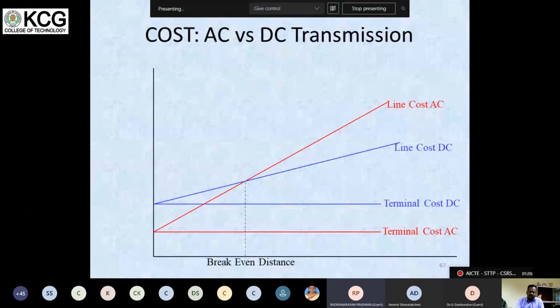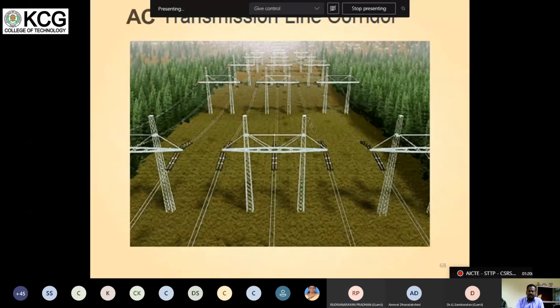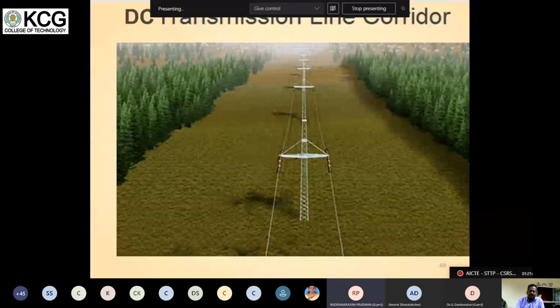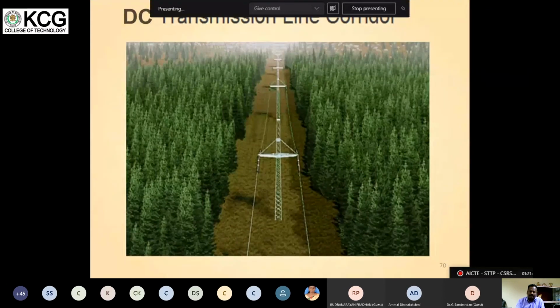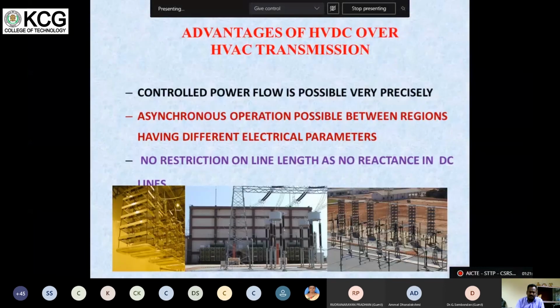Break even distance. This break even distance is around 600 km. So for more than 600 km, power transfer can be done with an HVDC system, which decreases the total project cost and losses also. So you can see here this many AC transmission tower lines can be replaced with only one HVDC transmission system. The land requirement is also very, very less, agriculture land need not be wasted, and agriculture can be done with the available land. This is a very big advantage of the HVDC transmission system.